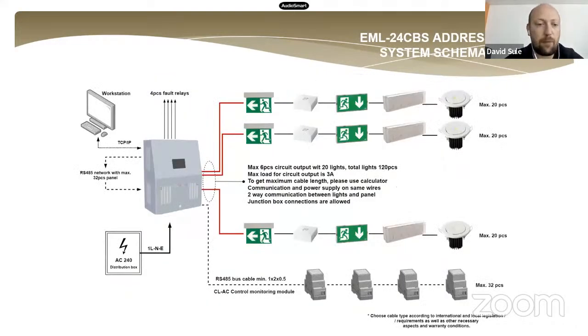This is a system schematic of the 24-volt DC addressable system. So we can see the panel needs a one-phase AC 230 or 240 AC input. It's one-phase, neutral and earth. The battery charger is inside the panel box, which gives the DC 24 volts for the charging and for the output of the lights.